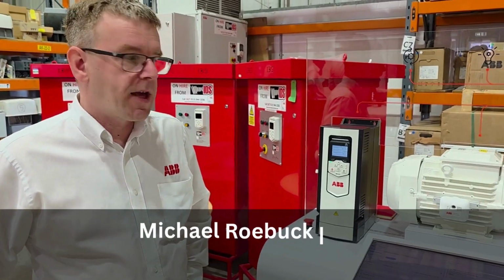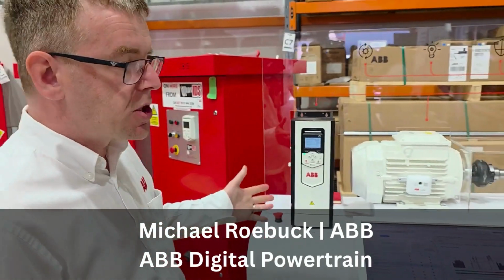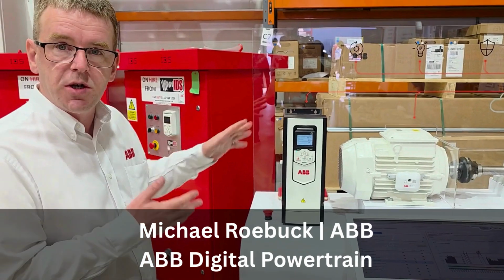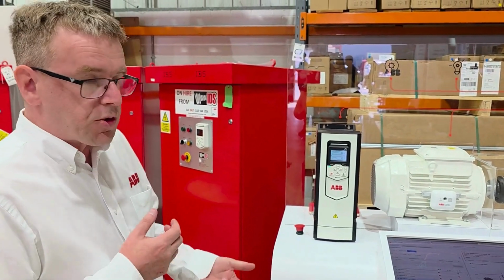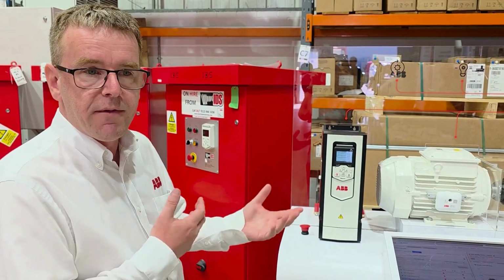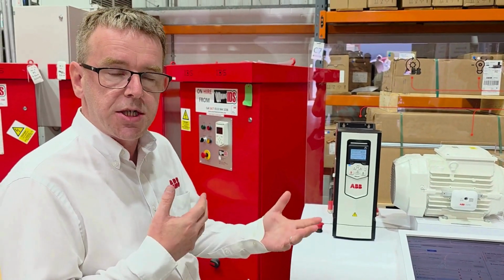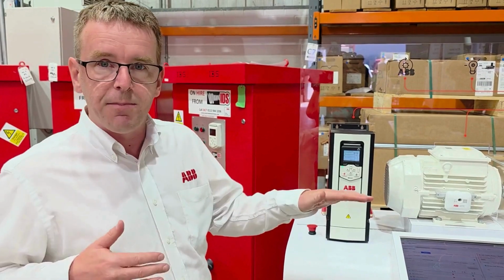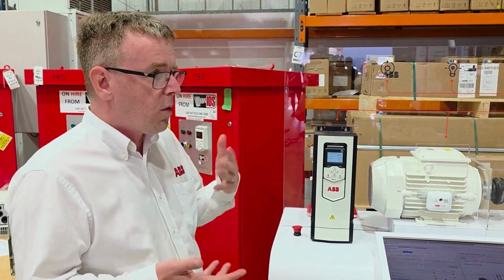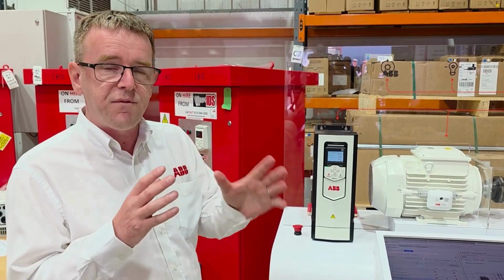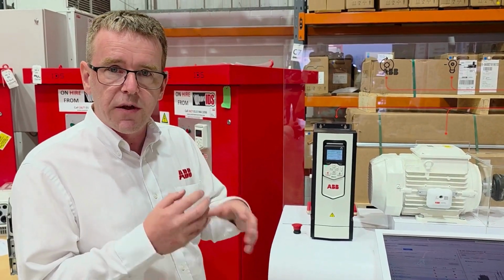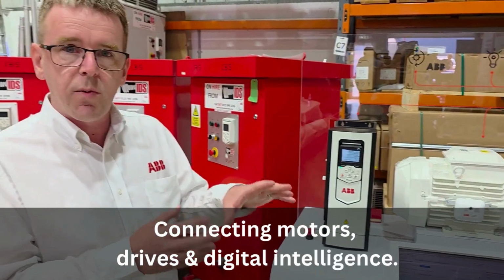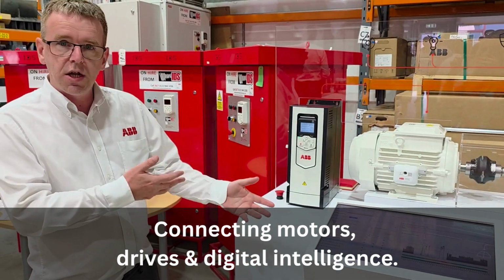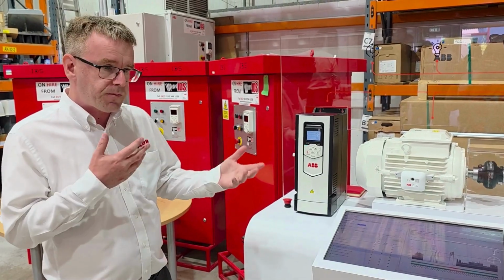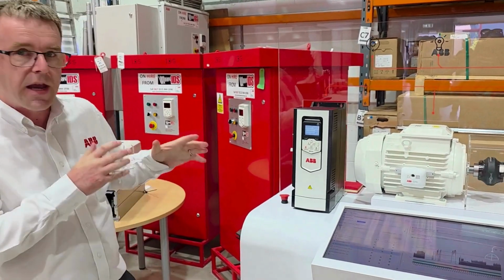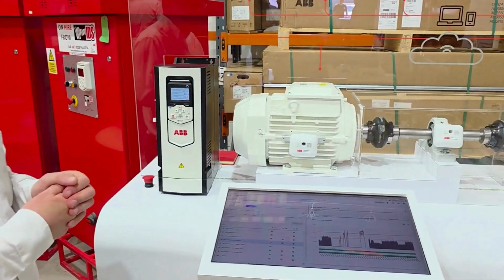This is our Powertrain portal rig, essentially drive condition monitoring. You're able to understand the health of the drive, the individual components, how they're aging, how the environment is affecting the health, how the application is affecting the health. A steady application with steady speed and steady current versus a cycle of load will actually affect how the IGBTs are rated in there. With the analytics and hardware we have, we're able to understand that and send a message to the customer to let them know how everything's going. Everything ties into our digital Powertrain portal.